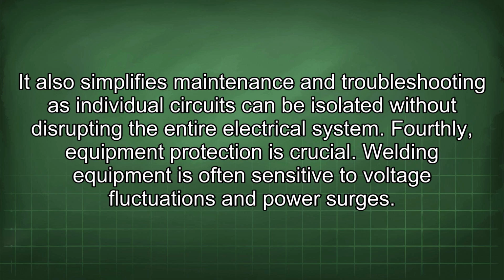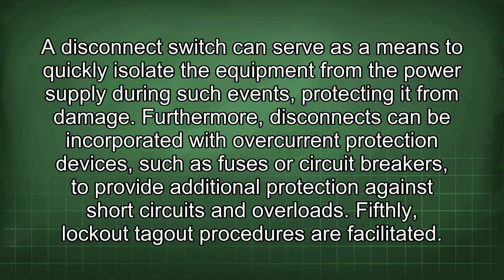Fourthly, equipment protection is crucial. Welding equipment is often sensitive to voltage fluctuations and power surges. A disconnect switch can serve as a means to quickly isolate the equipment from the power supply during such events, protecting it from damage. Furthermore, disconnects can be incorporated with overcurrent protection devices, such as fuses or circuit breakers, to provide additional protection against short circuits and overloads.